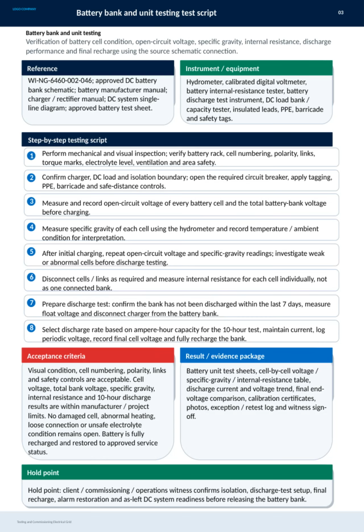On this slide, we focus on the comprehensive testing procedure for the battery bank and individual units. The core goal is to verify several critical parameters, including battery cell condition, open circuit voltage, specific gravity, internal resistance, discharge performance, and final recharge, all aligned with the approved schematic connections. We start with a mechanical and visual inspection to ensure everything from the battery rack to electrolyte levels and safety measures are in proper order. Then, safety controls like circuit breaker isolation, tagging, PPE, and barricades are implemented before we proceed.